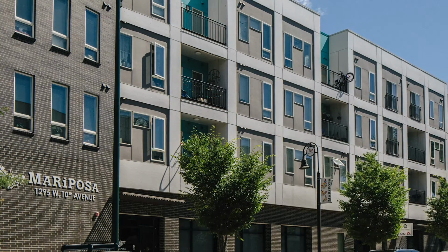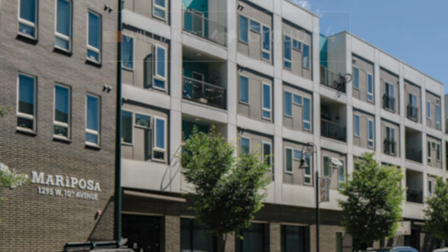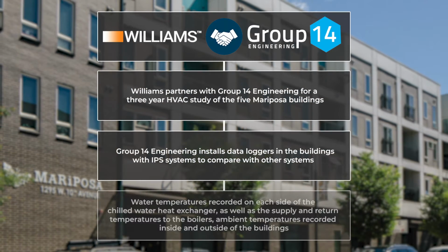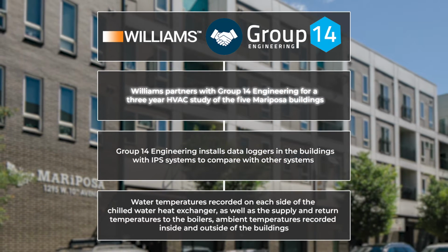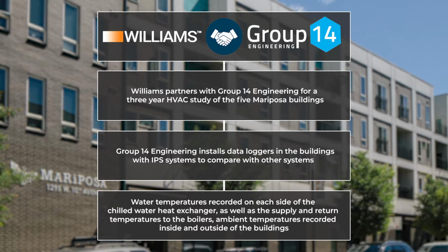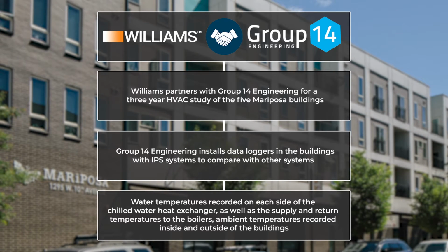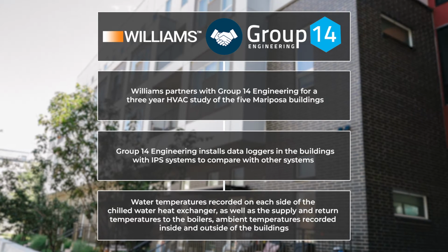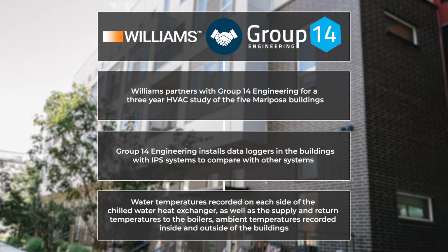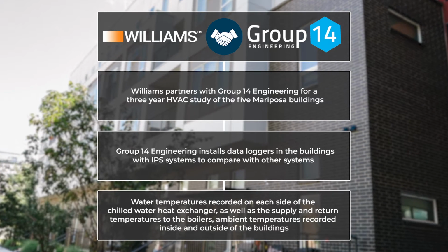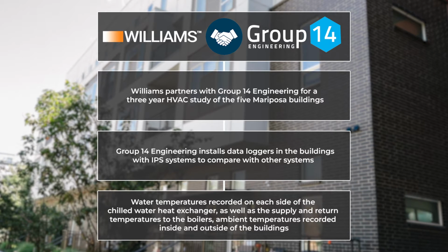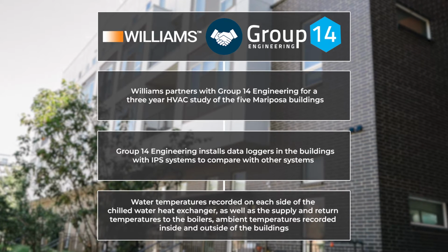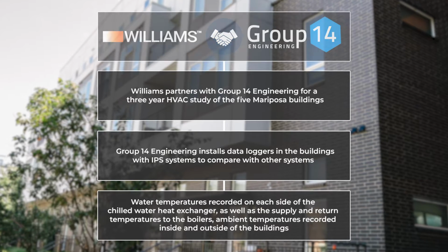To monitor performance for the different types of systems, Williams initiated a 3-year study and partnered with Group 14 Engineering, who installed data loggers throughout the buildings with IPS systems installed. Water temperatures were recorded on each side of the chilled water heat exchanger, as well as the supply and return temperatures to the boilers, and ambient temperatures were recorded inside and outside of the buildings.